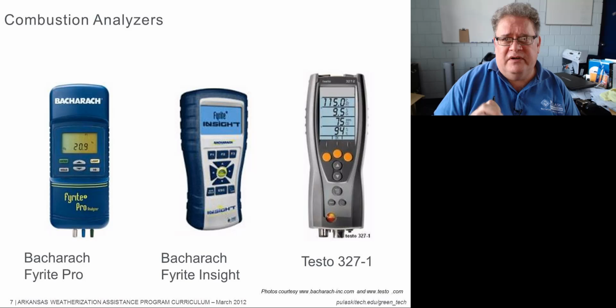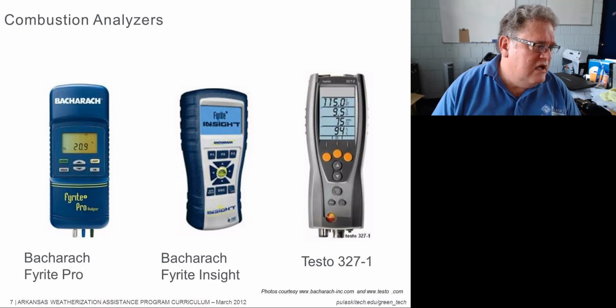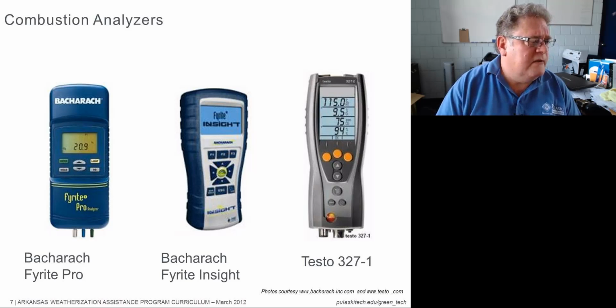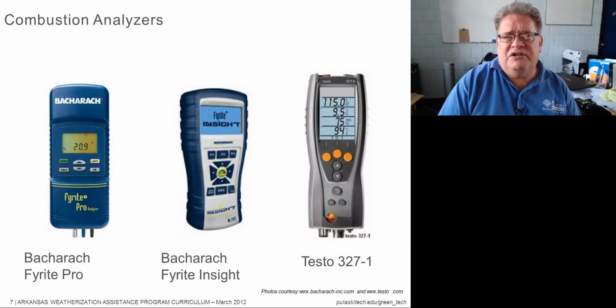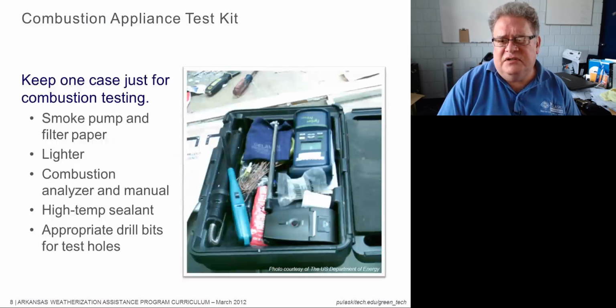I'm not going to get too deep into it, but some of the other brands, they may or may not be giving you as accurate a reading as possible. It has to do with this stoichiometric equation that they're using. They know better. I'll just say that I prefer one that reads CO or that has a CO sensor and an oxygen sensor, as opposed to a CO2 sensor and an oxygen sensor. That's just my preference. Okay, and then you've got a combustion appliance test kit. Now this should contain a lot of things.